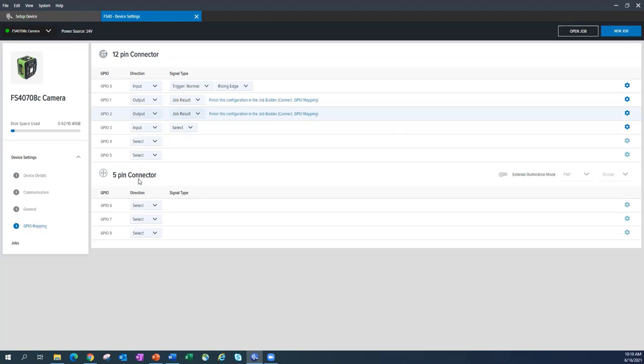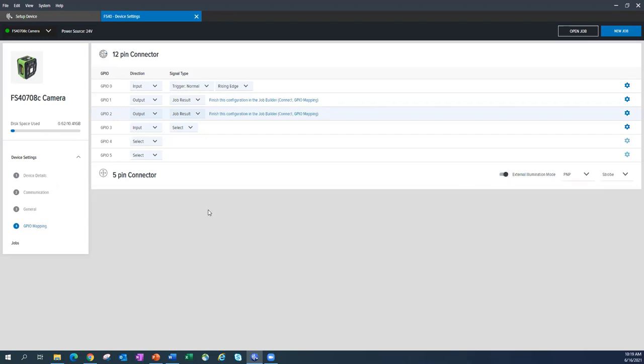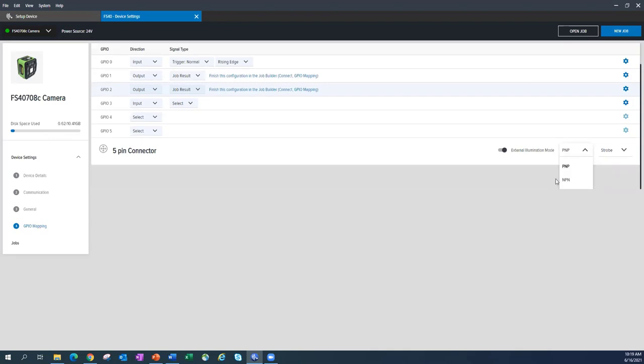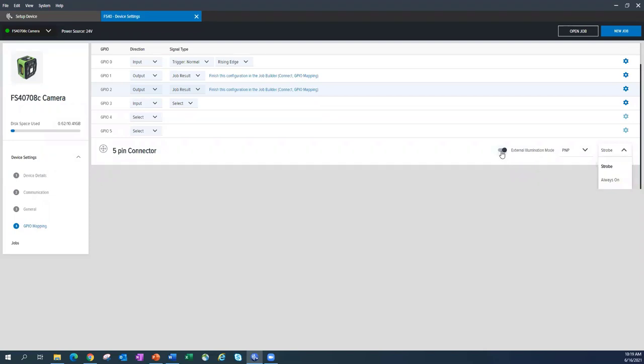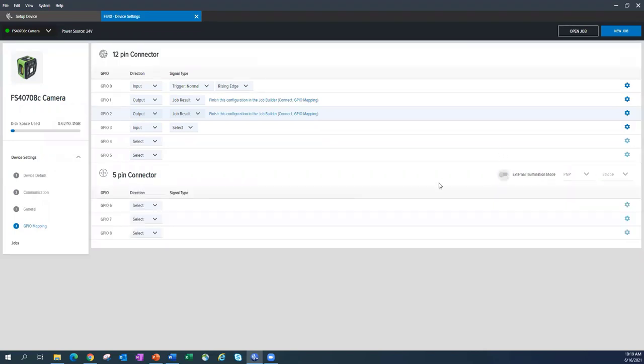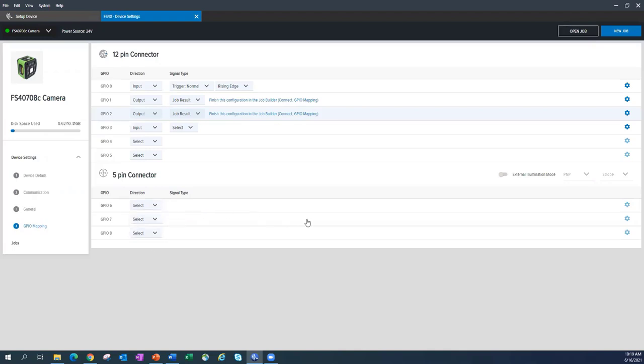You'll see there's a five pin connector. That's our third connector on the camera. So we have the ethernet, we have the 12 pin power connector, and then we have this five pin. This is a light control as well as additional IO that's available. So currently by default, I have my light control off. If I want to say, hey, I want this to power it and run an external light, I simply just click this button over here. You can see my GPIO options disappear. They're no longer there. And then I could say I want my light to be PNP or NPN controlled, or I want it to be strobed or continuously on. This is where you could come in here and adjust those settings on how you want to play with your external lights. If I'm not using any of the external lights, I simply turn this back off. And you see here, I have additional three GPIO that I have the capability to do different things. So again, just like above, I can make these inputs or outputs, and I could change the different types and signals and those sorts of things.